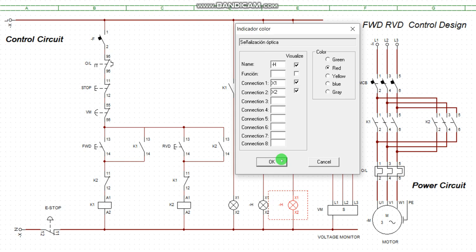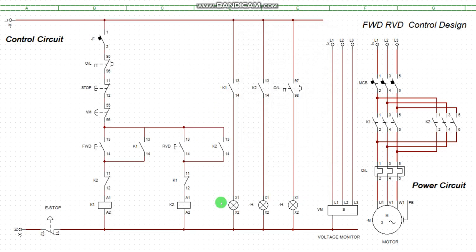Red. Then in some cases, we use alarm to indicate backward in some industry. But for production line, we don't need an alarm because the forward and reverse is already a normal operation. So we use it for normal operation. So you don't need alarm. Instead, you need a signal to know when the production line is going on reverse and when it is going on forward. Because some goods will be conveyed during forward operation and some goods will be returning back during reverse operation. All right, so in that case, you can now visualize what is happening within the conveyor.